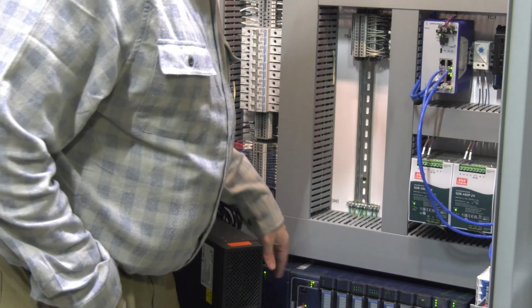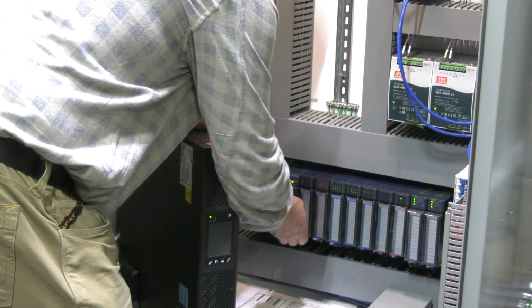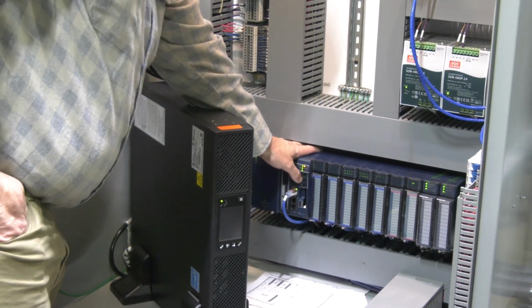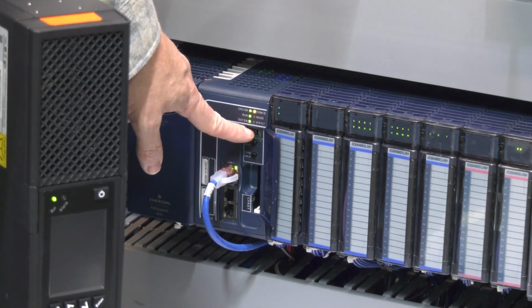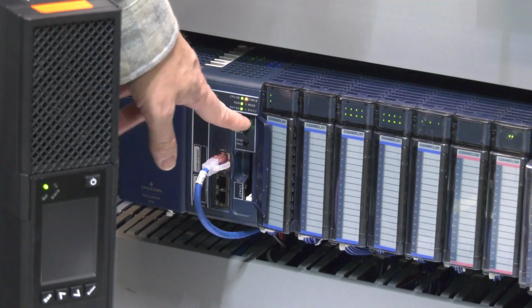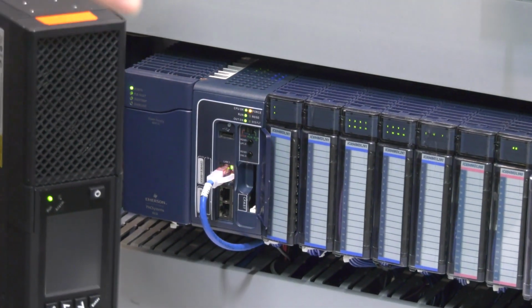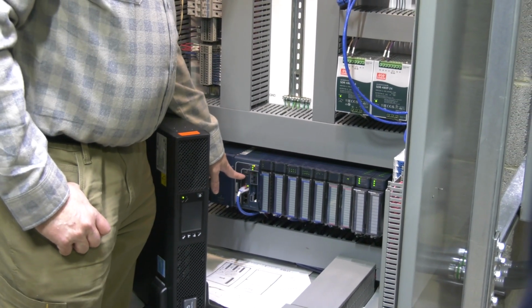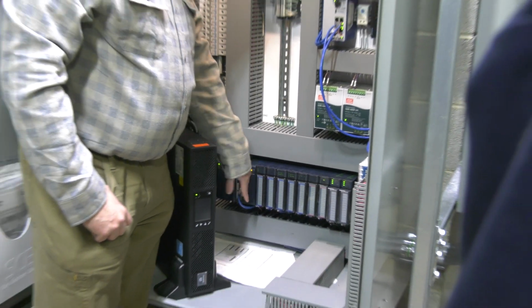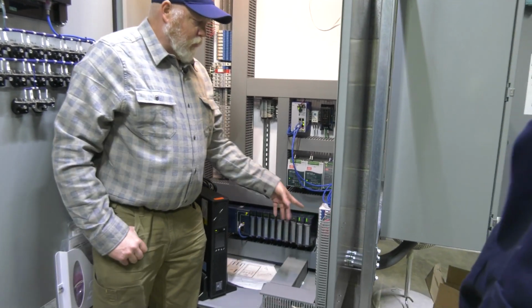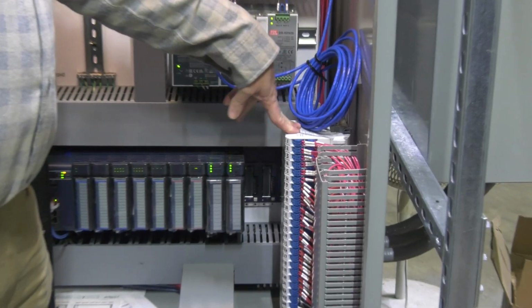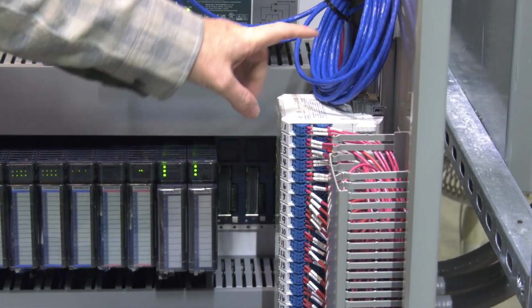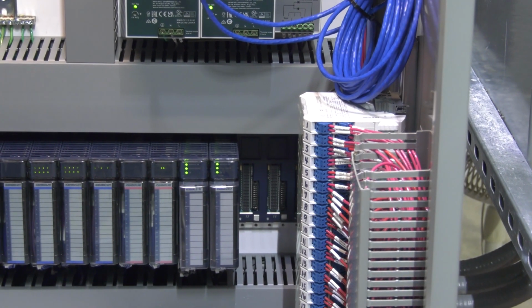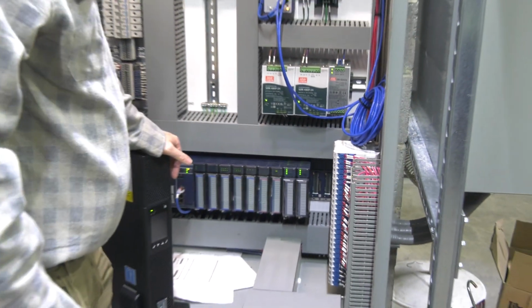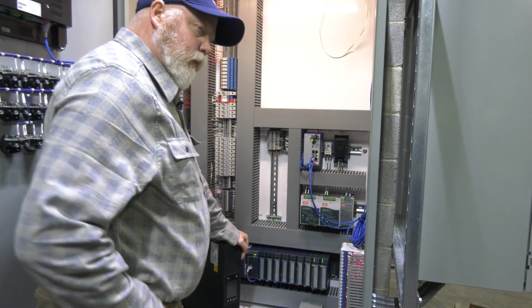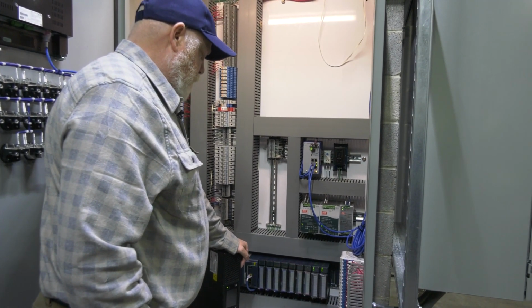Your PLC's right here. The only thing that you guys probably might really need to know about is you've got a switch here to stop, to take the PLC out of run mode, and then you can run it without outputs on, or run it with outputs. You want to keep it run with outputs. So if you ever have a problem and nothing works, if this is ever replaced, make sure that switch is in run with outputs enabled. And right here, you've got your intrinsic safety barriers. These are mostly for your radar level transmitters and your limit switches downstairs. If you have any problems with those, I'm not sure if you guys have spare parts or not. We do, but I don't know to what extent. Right. I do know that they gave Cease a bunch of spare parts, but as to what extent, I do not know. Okay. All right.